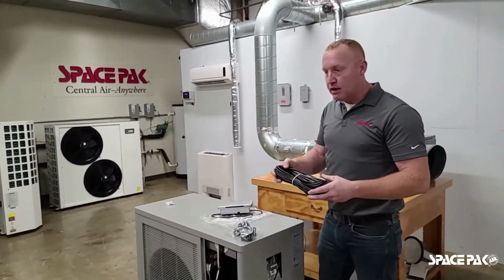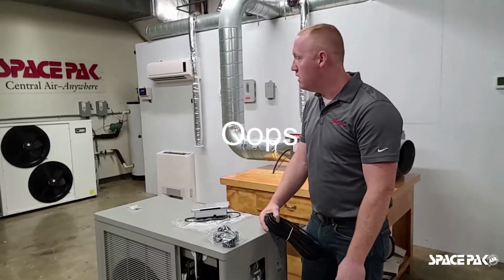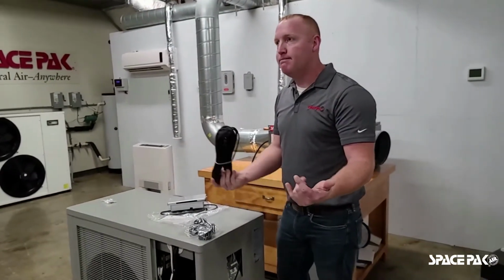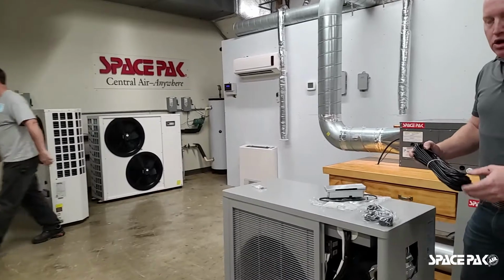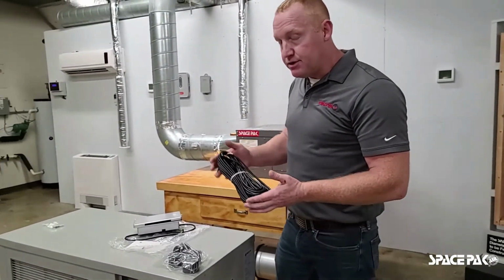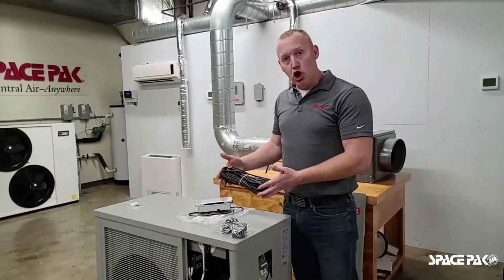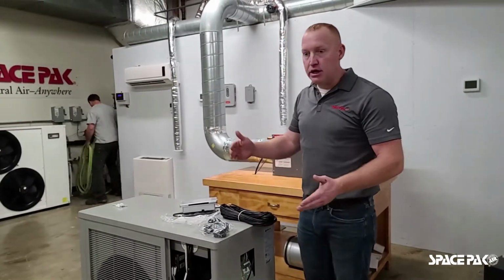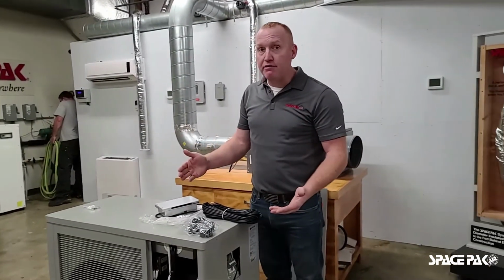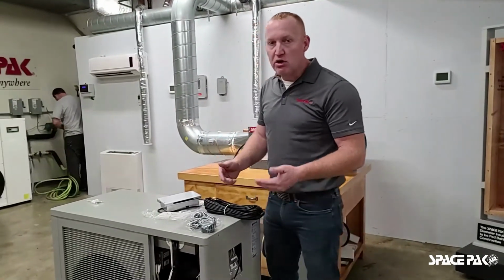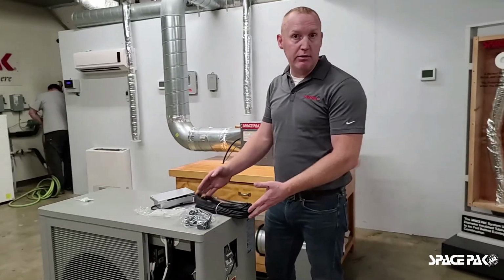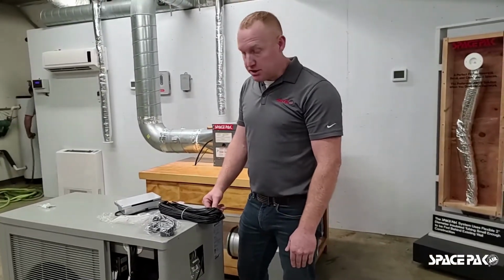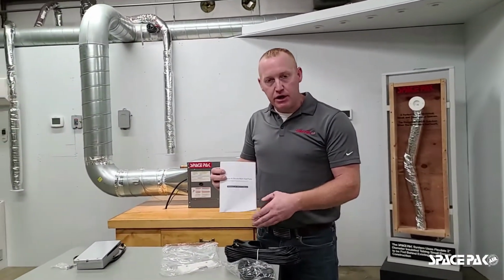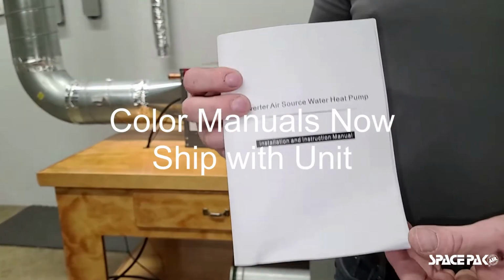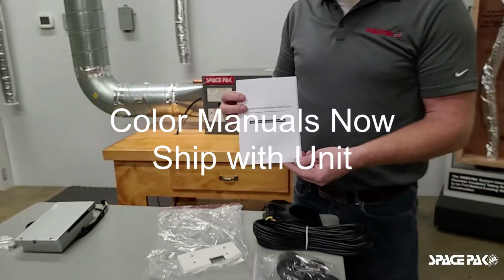We also have a supplemental piece that, not supplemental, what's the word? What's the word, Dan? So during the installation process, if we find that the 65 feet that we ship standard is not quite long enough for your particular application, this unit can actually be distanced from the controller up to 600 feet. And if that is the case, we need to stretch it out over our 65 feet. We have spec'd out a suitable equivalent as far as the wire is concerned that we can use. So that'll be listed right on our spec and data equipment sheets. Also coming with the unit is a small installation manual. Full color installation manuals are available on the SpacePak.com website, as well as through your local wholesaler and or local rep.